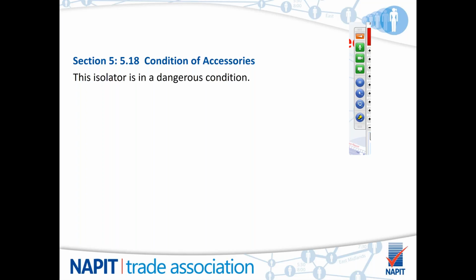It is obvious with the hole in the front of the isolator that people could put their fingers in. In fact, in that one, most of the hand. Access to live parts. If those live parts are touched, obviously injury will be on the cards. So immediate isolation is required. You need to get in touch with the customer, tell them what you're going to be doing, make sure that they are aware that it's being isolated and on what grounds you're isolating it.